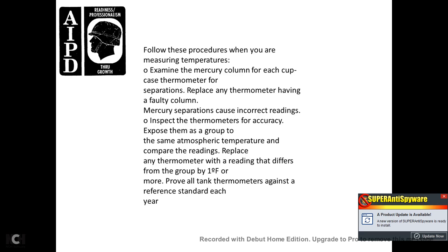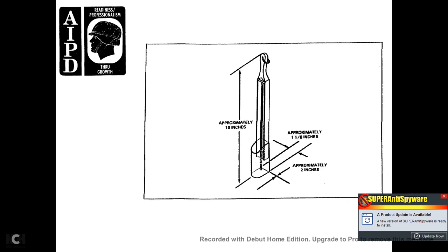Inspect thermometers for accuracy by exposing them as a group to the same atmospheric temperature, then compare readings. Replace any thermometer with a reading that differs from the group by 1 degree Fahrenheit or more. Prove all thermometers against a reference standard each year. The cup case thermometer is approximately 16 inches long, approximately 1 and one-eighth inches wide, and 2 inches deep.